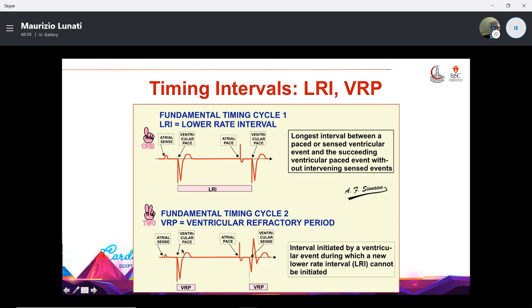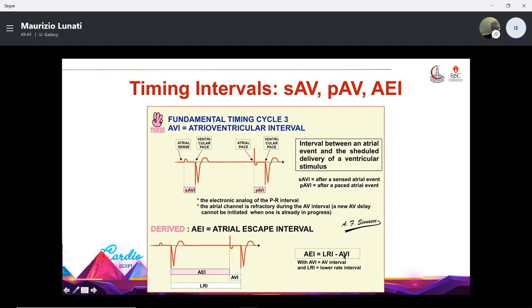Fundamental timing cycle 3: the atrioventricular interval, which is what in the electrocardiogram is the distance between the P wave and the QRS. We could have atrial sense and ventricular pace, or atrial pace and ventricular pace, or atrial pace and ventricular sense. The distance between the atrium and the ventricle is the AV interval, which could follow a sensed event in this case, or a paced event in these other cases. What is derived from the three fundamental timing cycles is the concept of the atrial escape interval, AEI. AEI is the lower rate interval minus the AV interval.